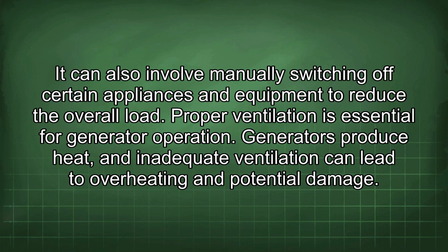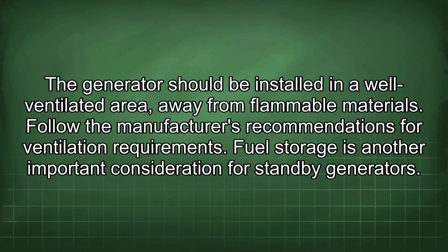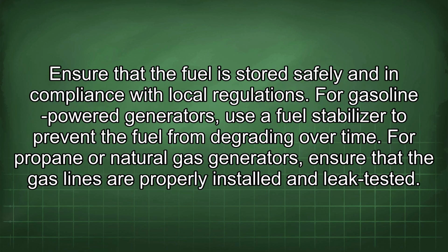Proper ventilation is essential for generator operation. Generators produce heat, and inadequate ventilation can lead to overheating and potential damage. The generator should be installed in a well-ventilated area away from flammable materials. Follow the manufacturer's recommendations for ventilation requirements. Fuel storage is another important consideration for standby generators. Ensure that the fuel is stored safely and in compliance with local regulations. For gasoline-powered generators, use a fuel stabilizer to prevent the fuel from degrading over time. For propane or natural gas generators, ensure that the gas lines are properly installed and leak tested.